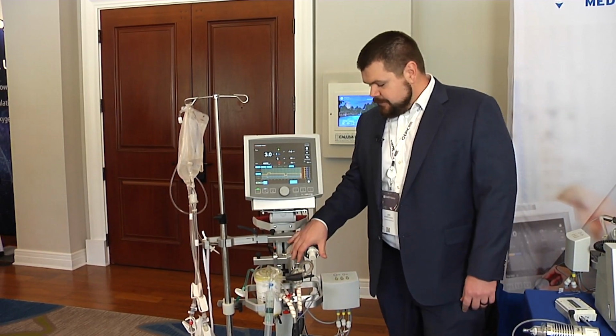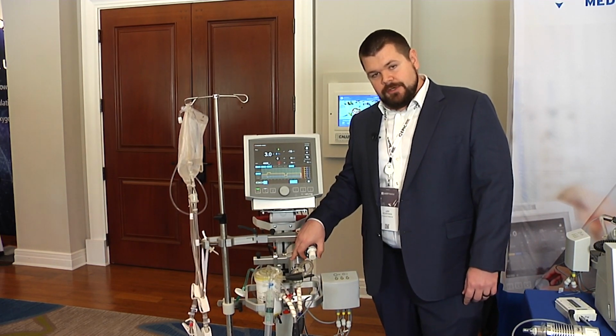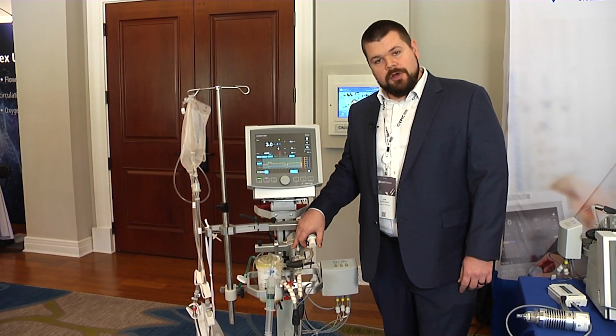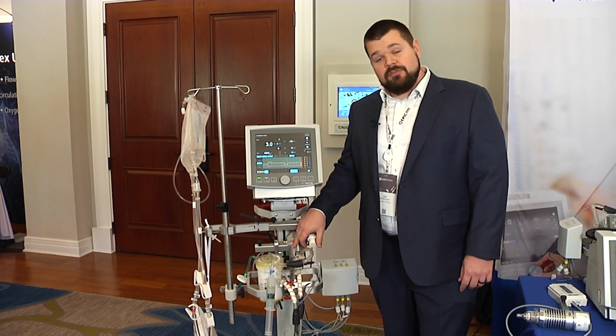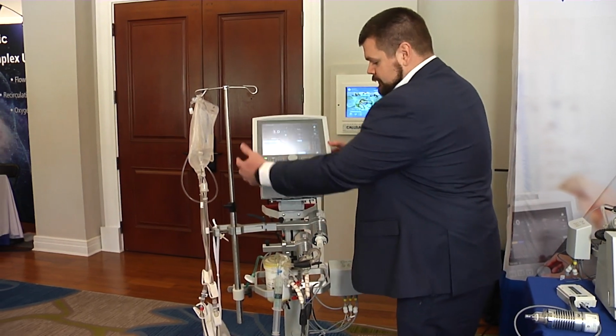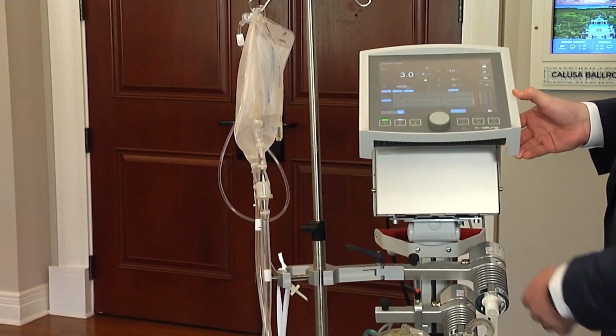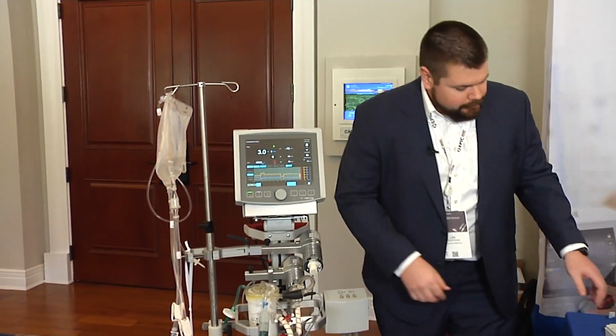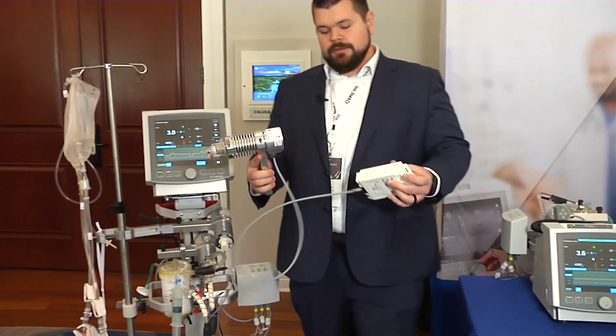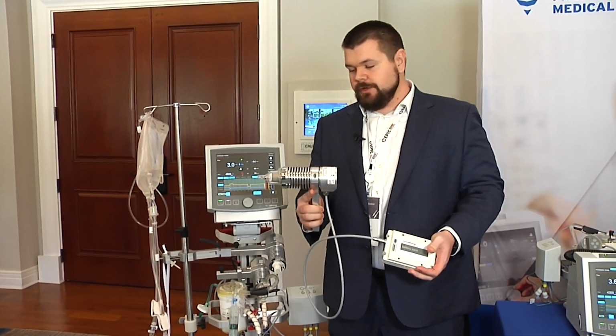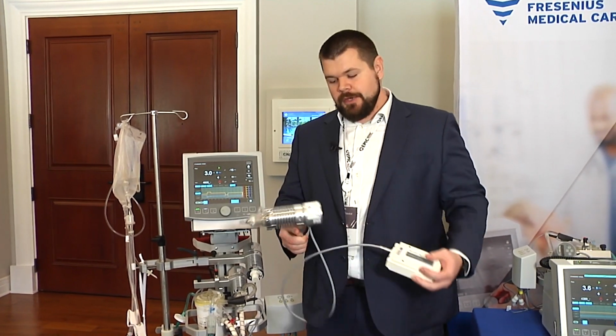And lastly, you'll see that we've got two identical pumps here. One serves as your backup pump in case of pump drive failure, and you can even plug it directly into a battery that lives underneath the screen here in the case of console failure, and that's what you see here. So this is one of our pumps plugged directly into a battery, spinning a pump head.